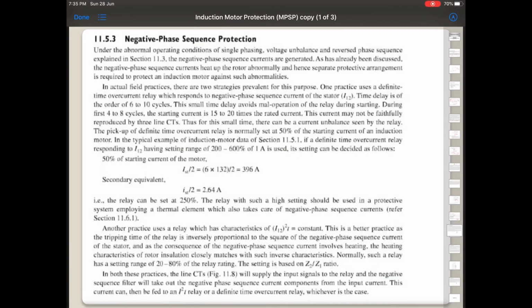Now we'll see negative phase sequence protection. So we already know that negative phase sequence currents are generated for single phasing, voltage unbalance and reversed phase sequences, and these negative phase sequence currents heat up the rotor abnormally, and hence a separate protective arrangement is required to protect the induction motor against such abnormalities. Now in actual field practice there are two strategies for negative phase sequence protection.